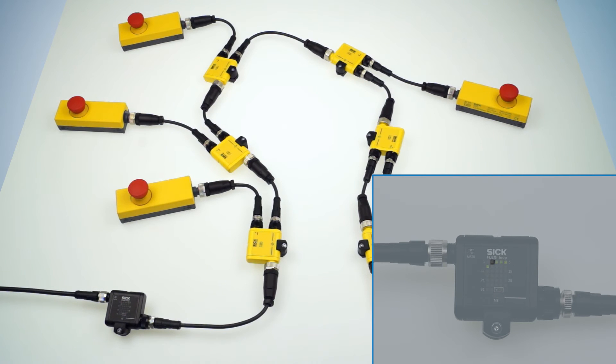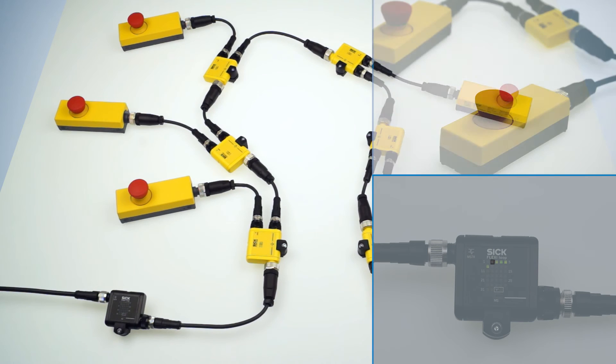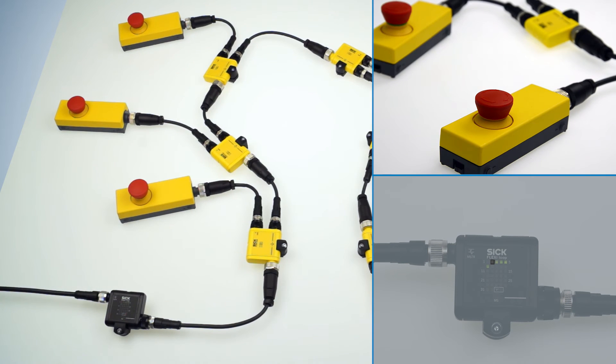Node LED 2 is flashing green. Again no error, but this e-stop has been actuated. So we release the e-stop and the LED stops flashing. Now here is also everything okay.